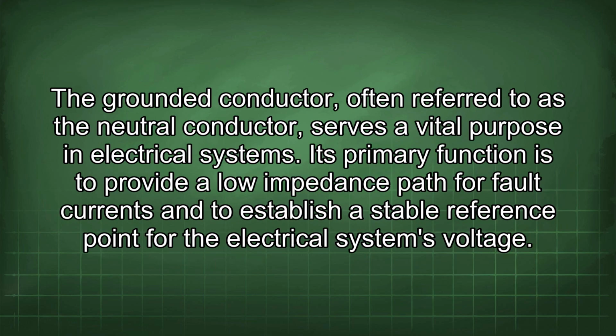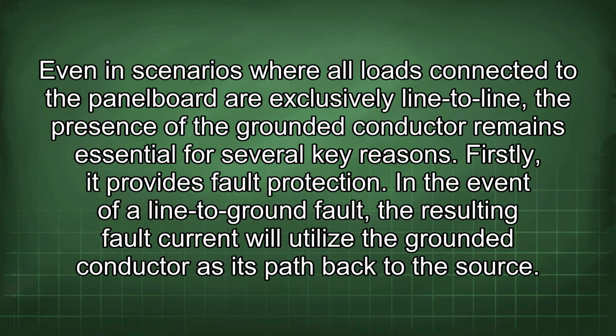The grounded conductor, often referred to as the neutral conductor, serves a vital purpose in electrical systems. Its primary function is to provide a low impedance path for fault currents and to establish a stable reference point for the electrical system's voltage. Even in scenarios where all loads connected to the panel board are exclusively line-to-line, the presence of the grounded conductor remains essential for several key reasons.